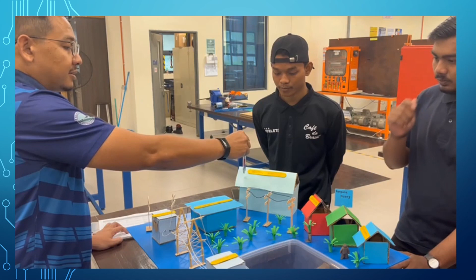There must be another small substation or step down transformer, 33 to 11 kV, and then maybe from 11 kV underground cable goes to commercial. So step down to 11 kV, make use of 6.6 kV for instance, or still another 11 kV also can, and then that 11 kV steps down to 415.